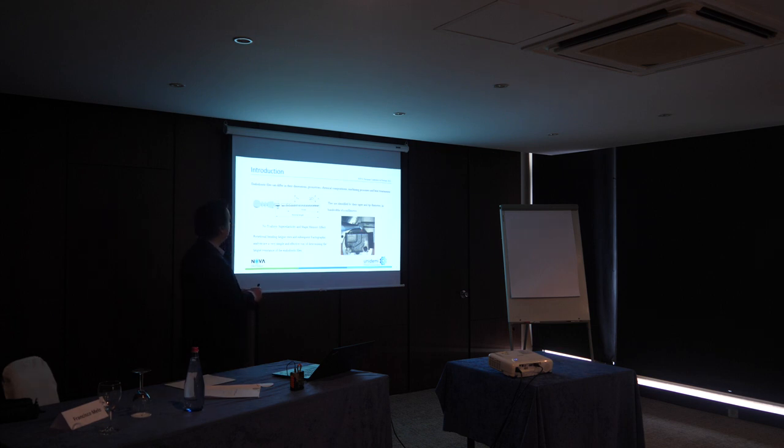The endodontic files differ in dimensions. For instance, the nominal length can be equal to 25 millimeters, but can also be 21 or 30 millimeters. The active length is 16 millimeters, and files are identified by the taper and the tip diameter. The endodontic files also differ in geometries: the cross section can be, for instance, a square, a rectangle, or a complex shape. They differ in chemical compositions, machining processes, and heat treatments. Those endodontic files are now made of nickel titanium alloys, which show superelasticity and shape memory effects. Typically we use rotational bending fatigue tests to assess their fatigue resistance.